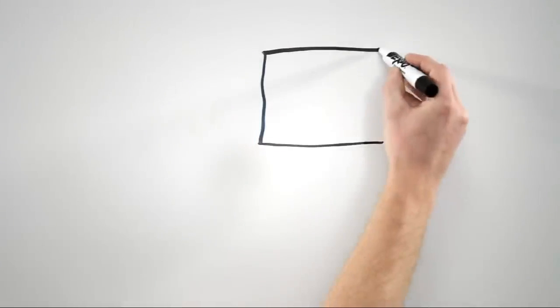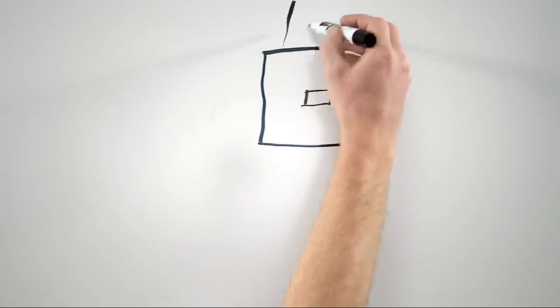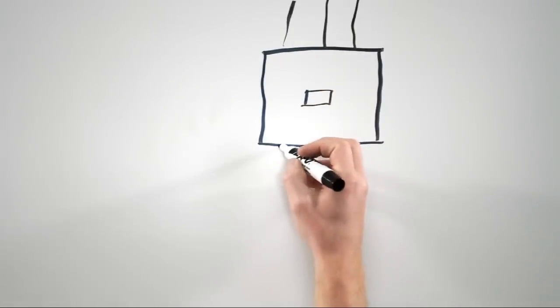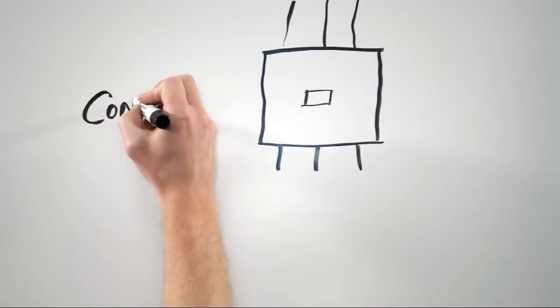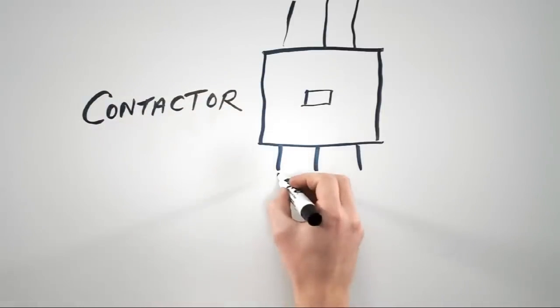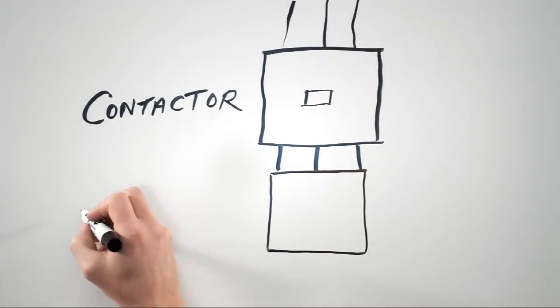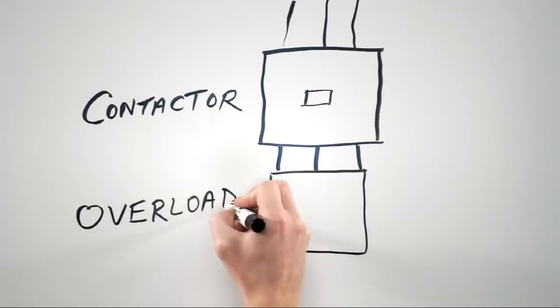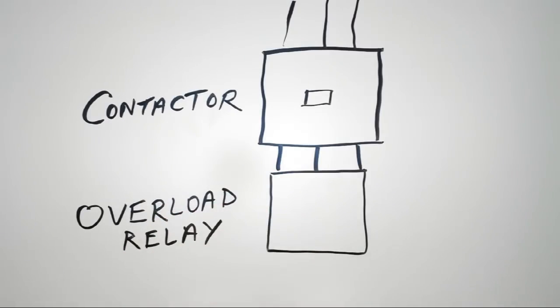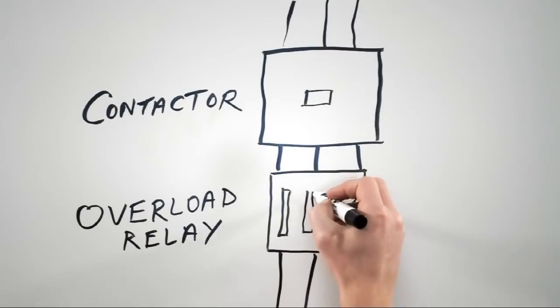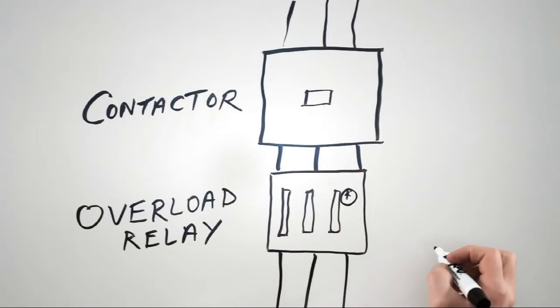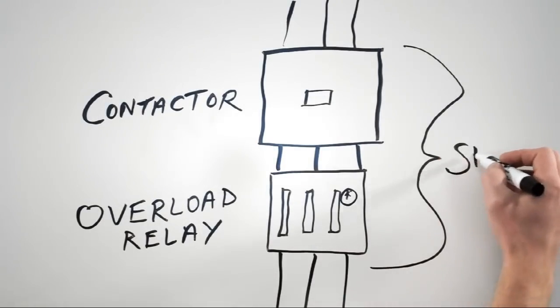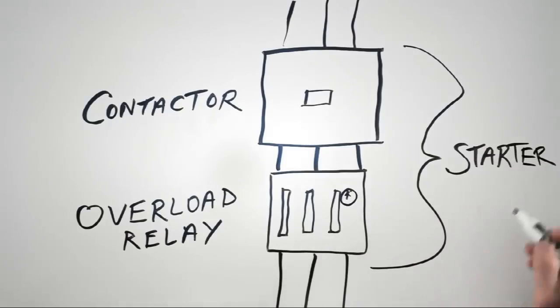So, if we get rid of the over current protection provided by the molded case breaker, we still need to find a way to protect the motor from an overload condition. Here we've got a contactor with our power coming in the top and out the bottom. But now let's add a new component to the contactor. This is called an Overload Relay. The Overload Relay has three bimetal strips inside, that are designed to heat up at the same rate as the windings of the motor. This is different from the bimetals inside the breaker, because those bimetals didn't know to ignore the inrush when you start the motor. When you pair an Overload Relay with a contactor, we call this a starter.